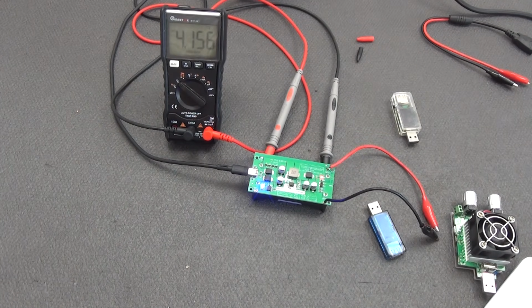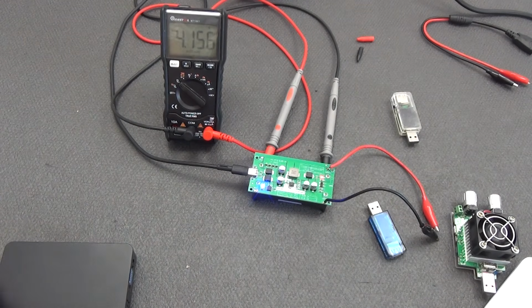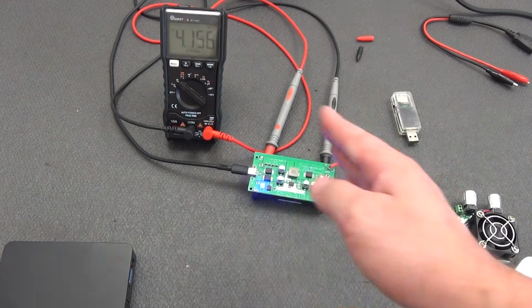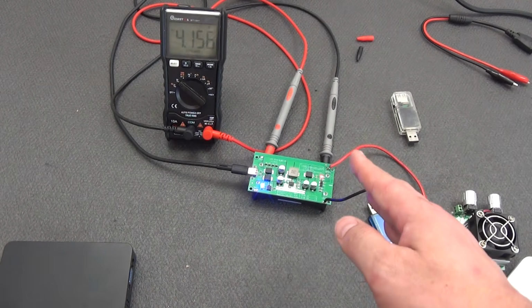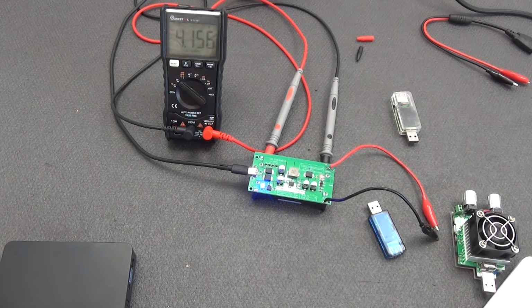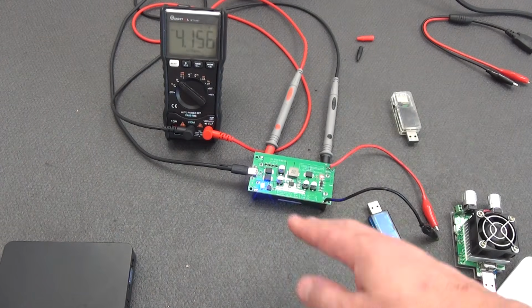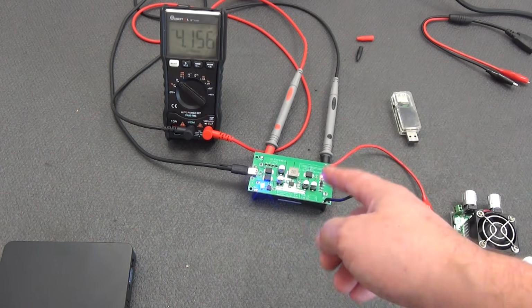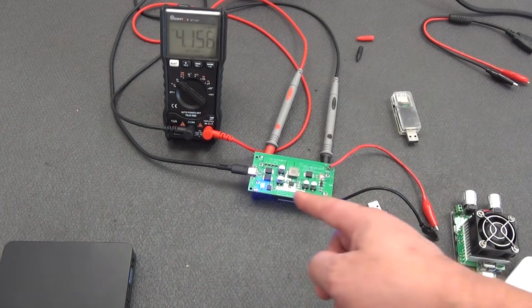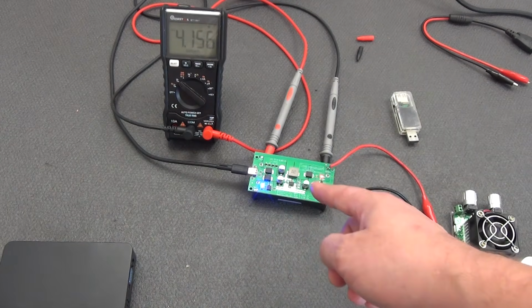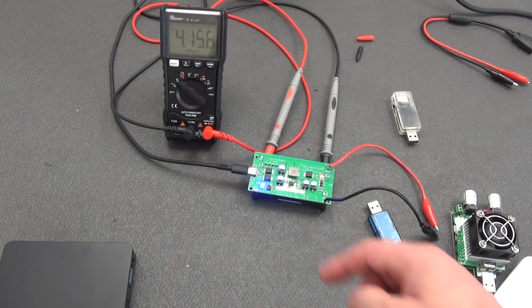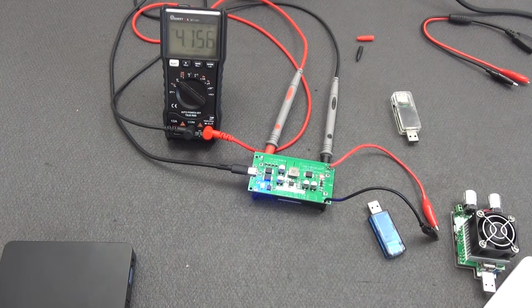It's also worth noting that this UPS works absolutely seamlessly. Switching between mains power and batteries happens instantly and is completely invisible to connected devices. The presence of capacitors at the output helps smooth even minor voltage dips, so devices do not reboot and continue operating without interruption. Moreover, when the batteries are fully charged and mains power is available, the connected load is powered not from the batteries but directly from the mains, which reduces battery wear and extends their lifespan. In this case, the batteries simply remain in standby and charging mode.